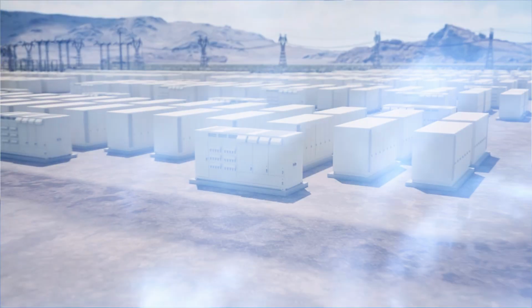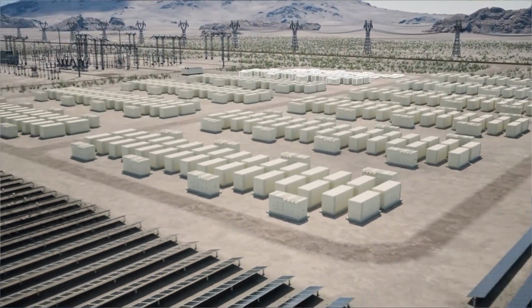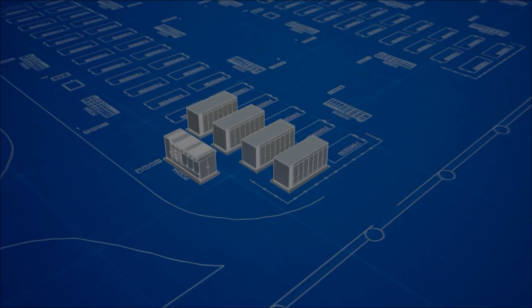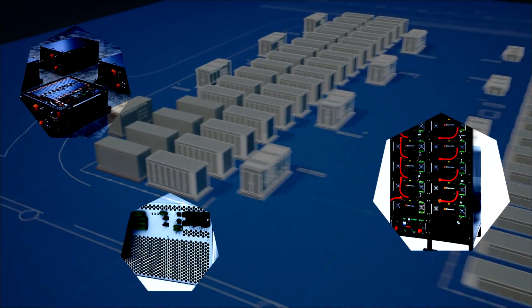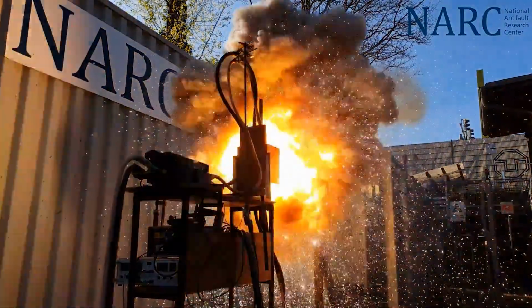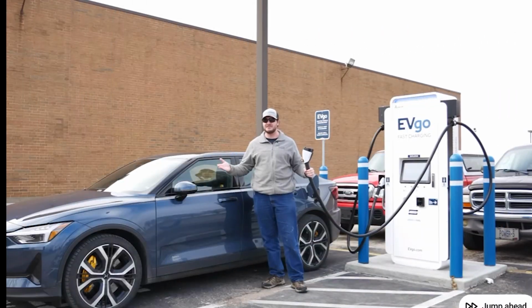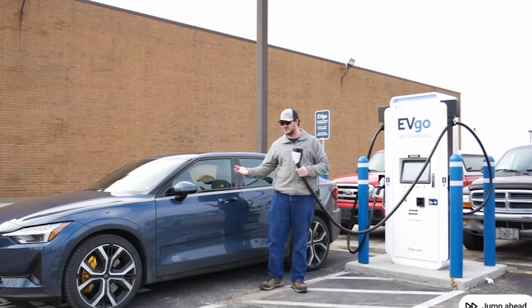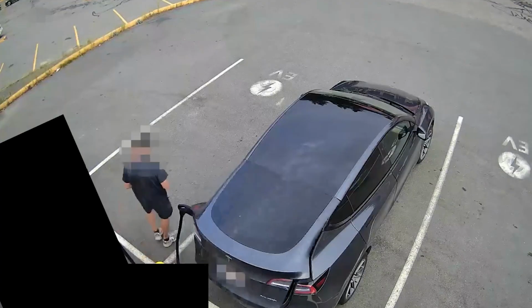The same DC protection challenge exists beyond AI data centers. Take the battery energy storage system industry, in which we have DC battery packs, DC racks, power conversion systems, and the DC bus, which needs to be protected from DC faults and short circuit current. Another industry is EV charging. Fast EV chargers of around 400 volts DC or higher need to protect the EV charging stations and the battery packs of the vehicle from the same DC overcurrent or short circuit faults.